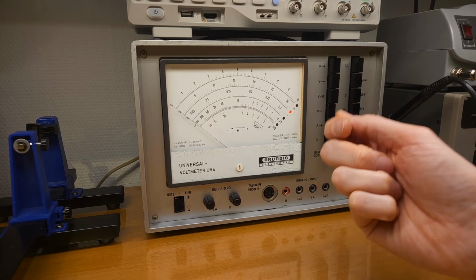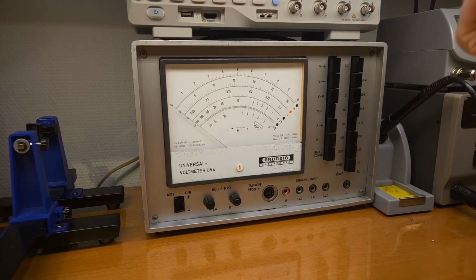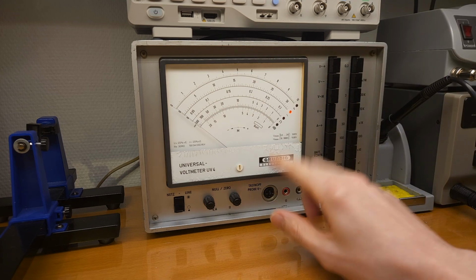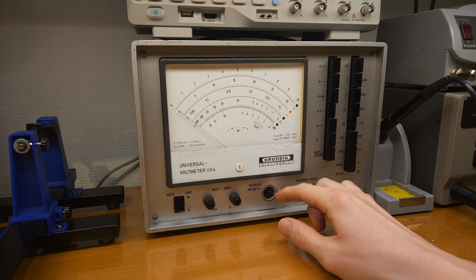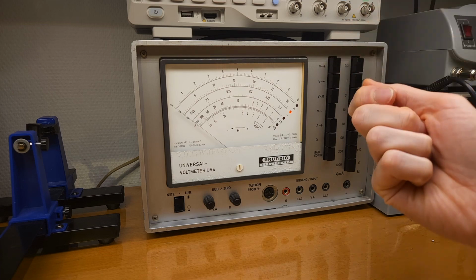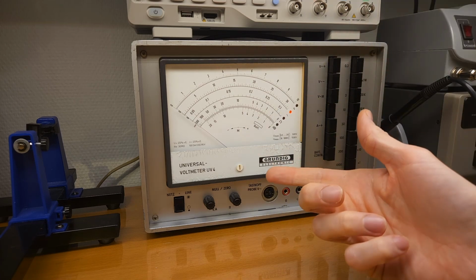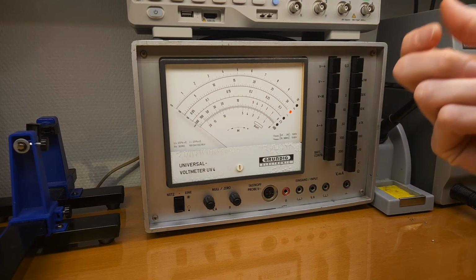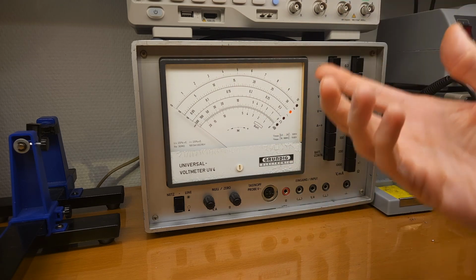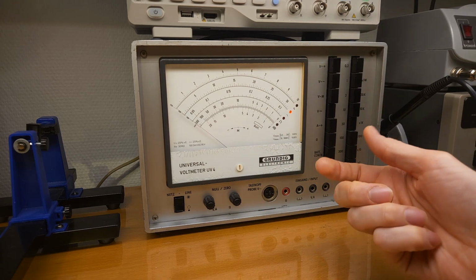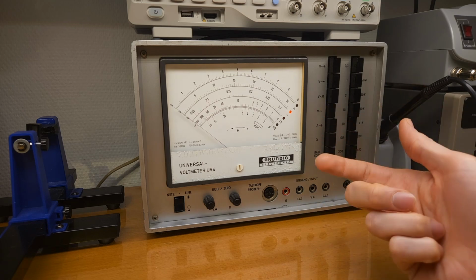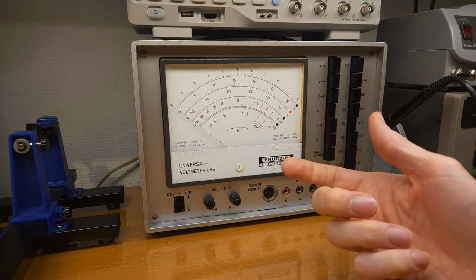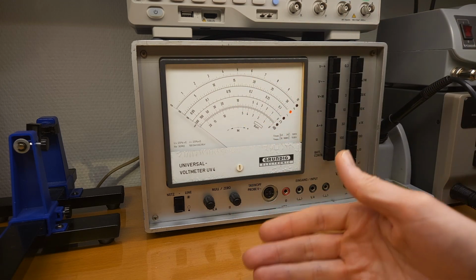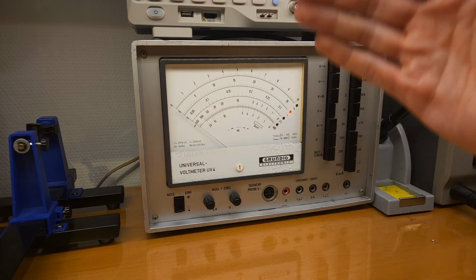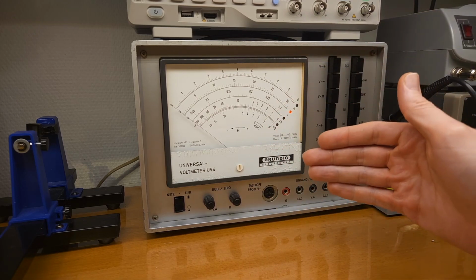Now what that test probe simply did was rectify the voltage. So then the voltage that the meter sees is still simply DC. The rectification is done inside the probe. Why they did this is quite clear, because they wanted to support also higher frequencies. So this test probe, according to the specs, went up to 30 megahertz fully linear. Higher than 30 megahertz, I think they claimed it could go to 100 or 300 megahertz, but then you would have to factor in a couple of dB of losses.